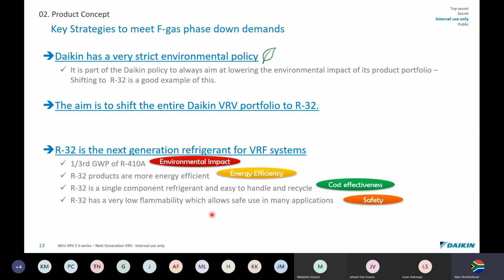R32 also has a very low flammability, which allows safe use in many applications. It is flammable, but we'll get on to that, and I'm sure you guys have seen a lot of presentations on R32. It doesn't burn like a cigarette lighter. It needs a lot of heat as an ignition source, and when you ignite it, the moment you pull the ignition source away, the R32 flame goes out. It doesn't self-combust.